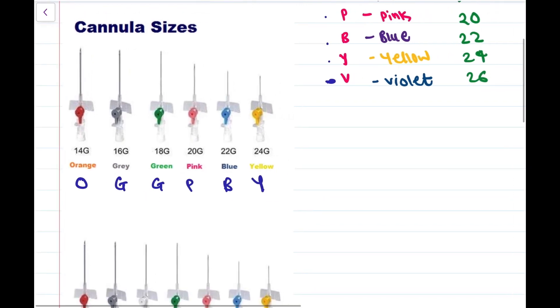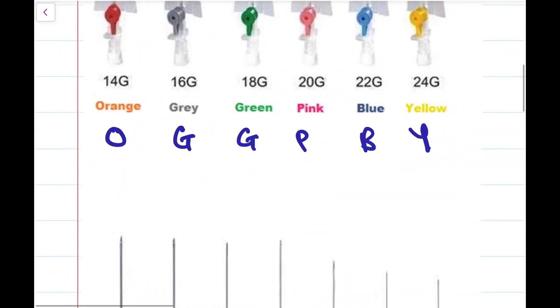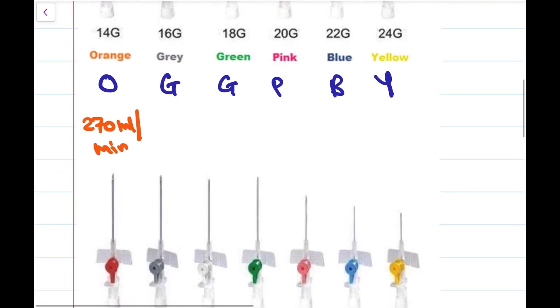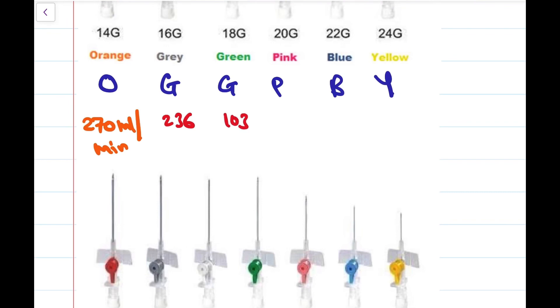Starting from orange, the flow rate is 270 ml per minute. The unit will remain the same for everything, that is ml per minute. For grey it is 236, for green it is 103, and for pink it is 67 ml per minute.